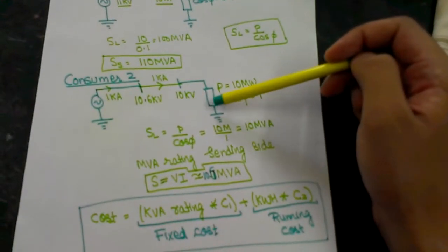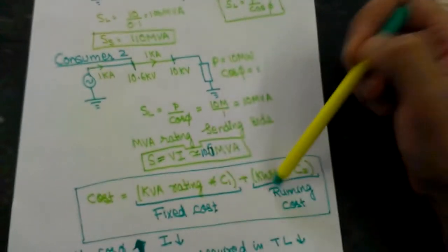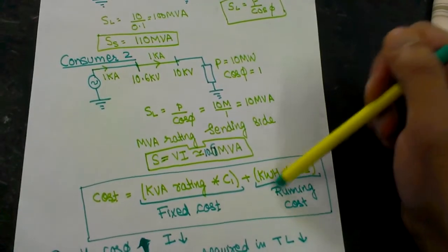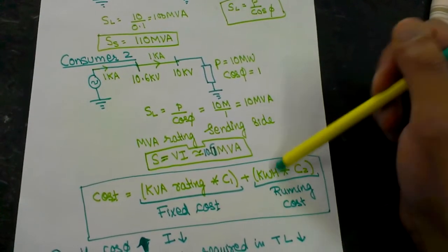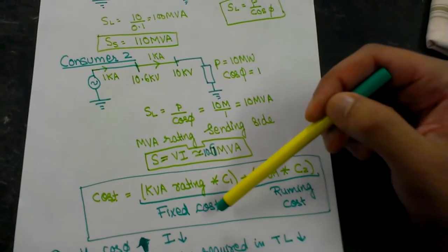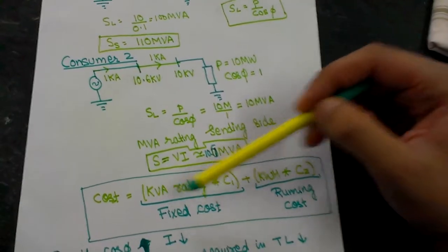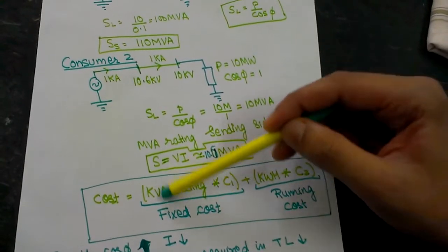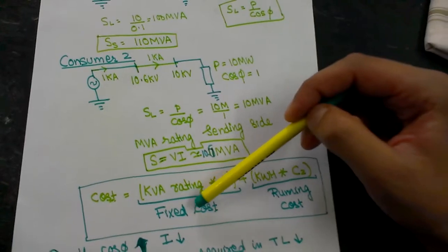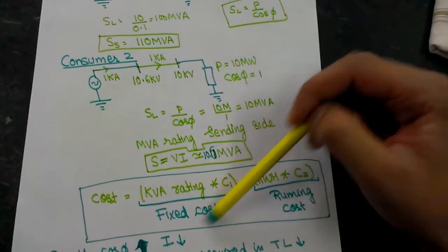That is why the poor power factor customer will be charged more. The cost equation depends on two factors: one is the fixed cost and the second is the running cost. The running cost depends on the watts (real power) you are consuming, while the fixed cost depends on the KVA (apparent power) you are consuming. This fixed cost depends on the power factor — so if you have a good power factor you will be charged less.